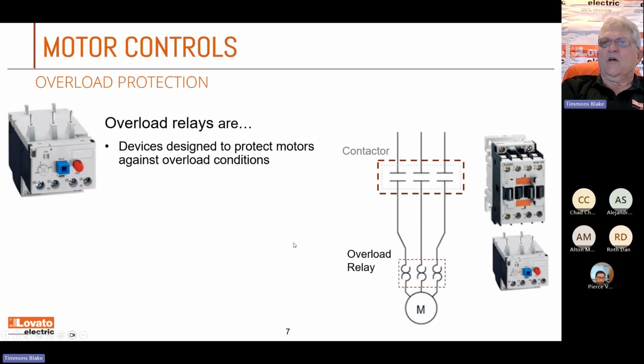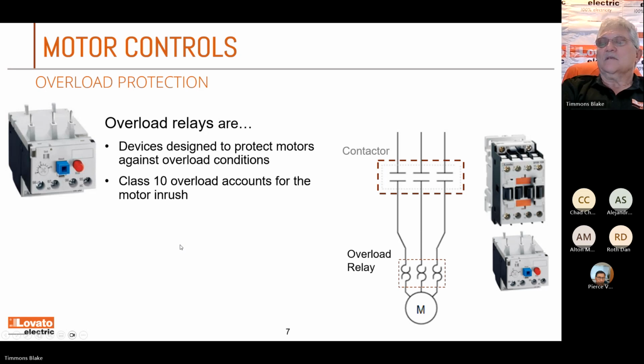Okay. A lot of people say, well, with this 10 amps I got on the overload, will that handle the motor? I said, yes, because these are what they call class 10 overloads. Takes 10 seconds at that rated current before it'll trip. So it handles the inrush of the motor. Okay.